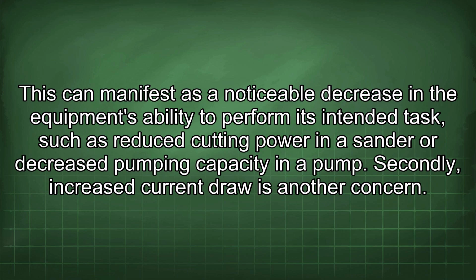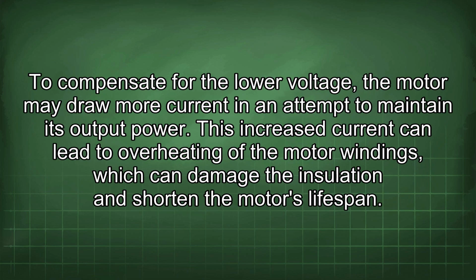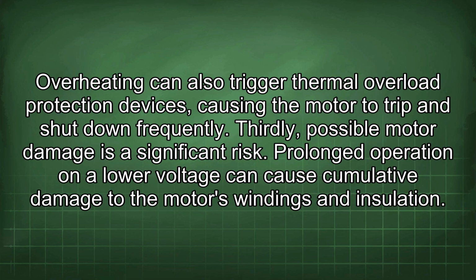Secondly, increased current draw is another concern. To compensate for the lower voltage, the motor may draw more current in an attempt to maintain its output power. This increased current can lead to overheating of the motor windings, which can damage the insulation and shorten the motor's lifespan. Overheating can also trigger thermal overload protection devices, causing the motor to trip and shut down frequently.